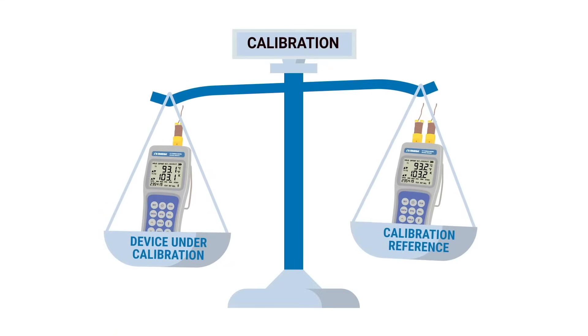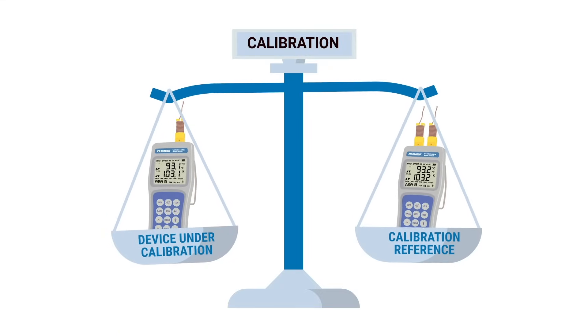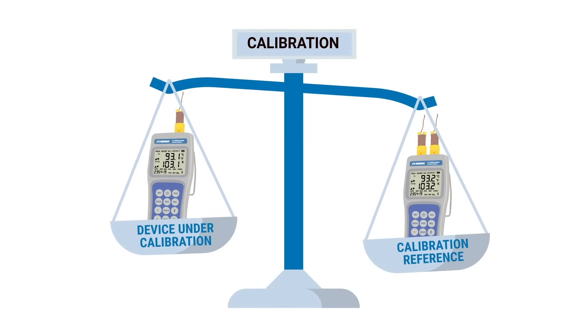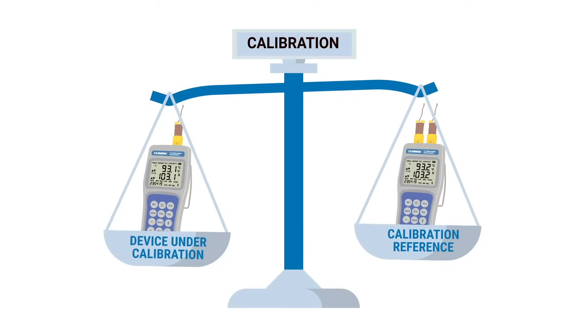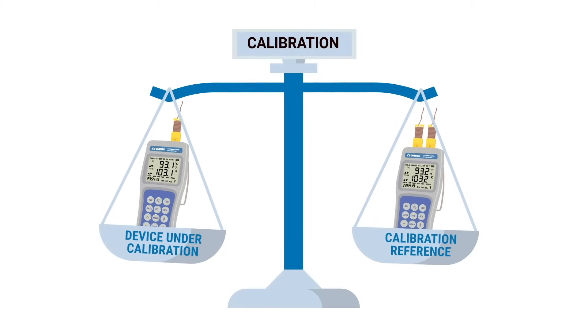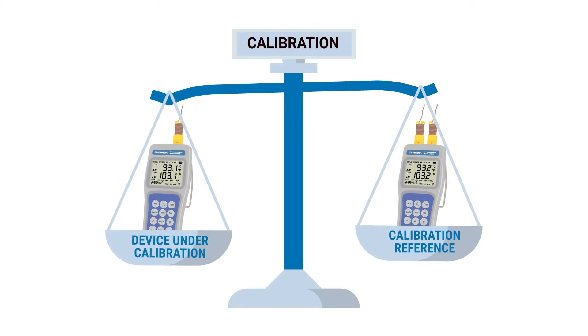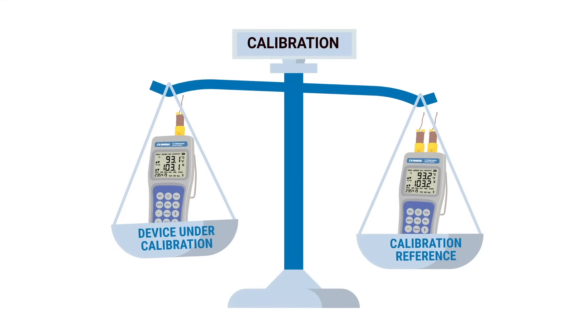Calibration is the comparison of a measurement value from a device under calibration with that of a known traceable calibration reference — typically a device that is more accurate than the unit being calibrated and with accuracy traceable to a recognized standard.